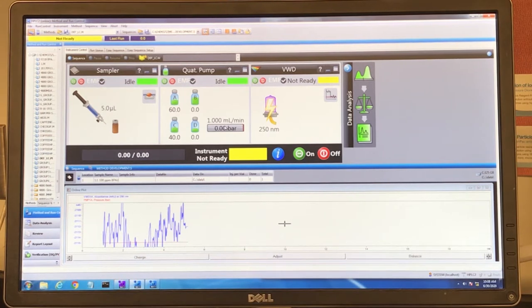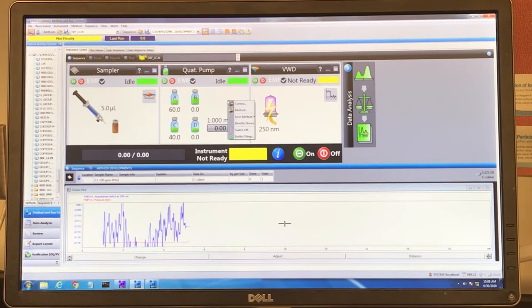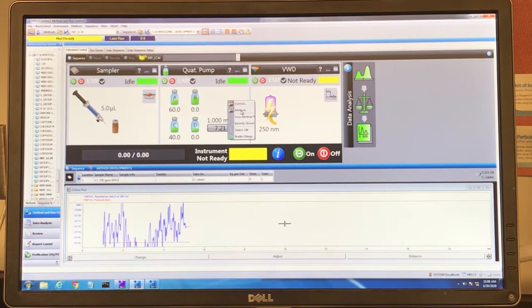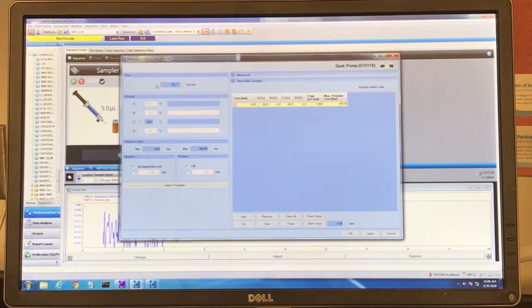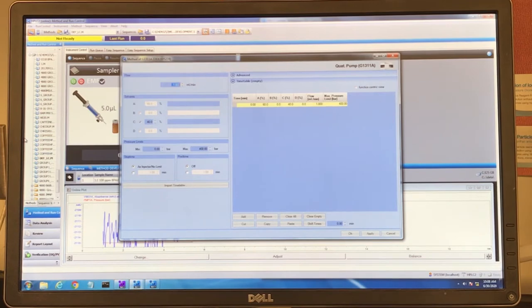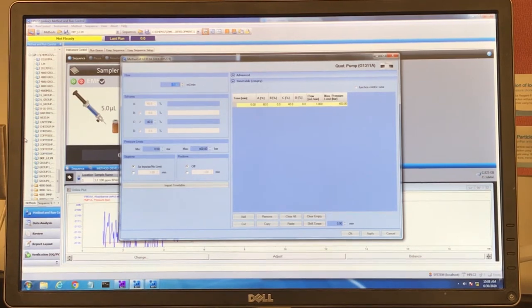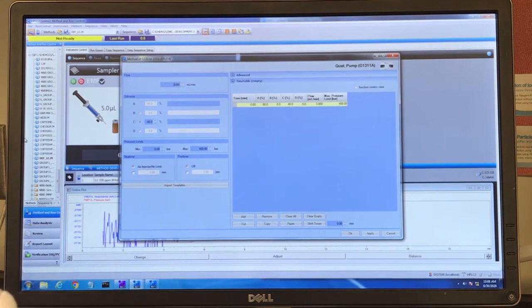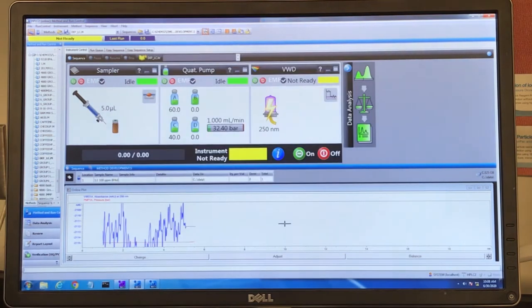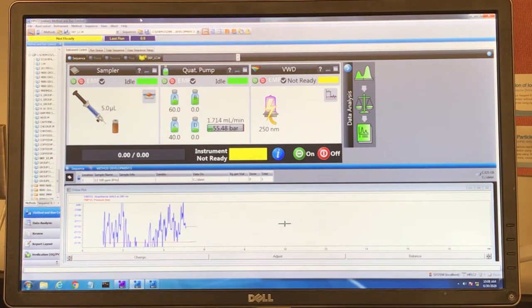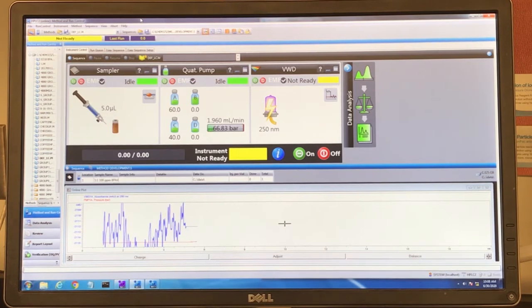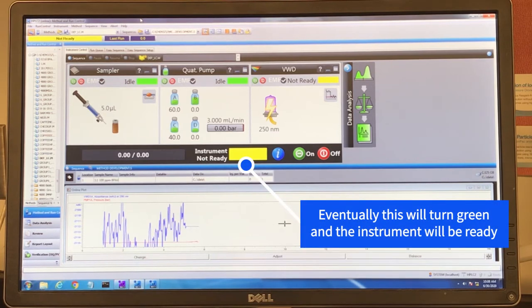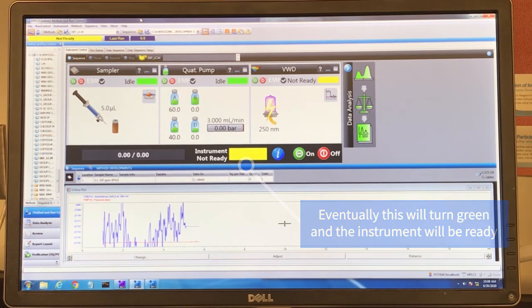The flow rate is right now listed at 1 mL per minute. If you right-click inside the quaternary pump box and then click Method, you can change this flow rate. If the instrument hasn't been run in a while, it's useful to increase the flow rate to about 3 mL per minute to get a nice purge on the pump itself and make sure all of that solvent is being directed to the waste.